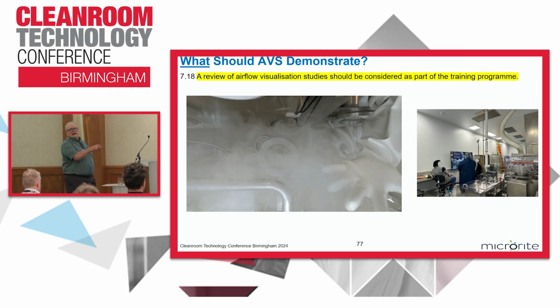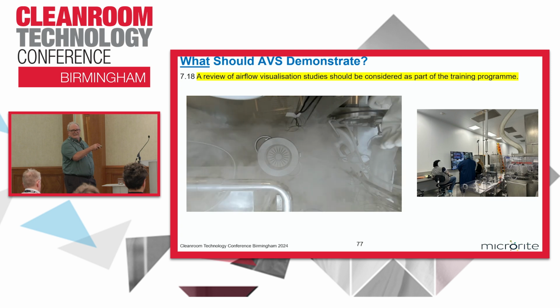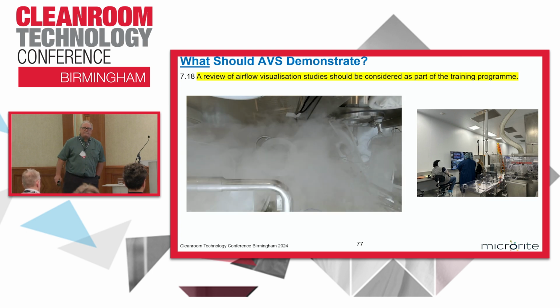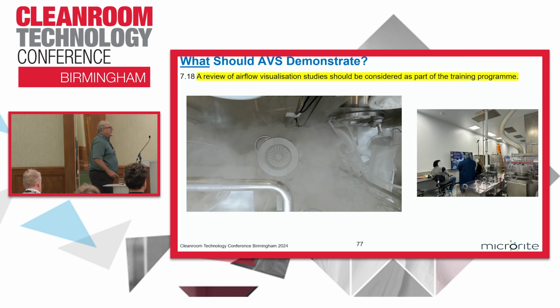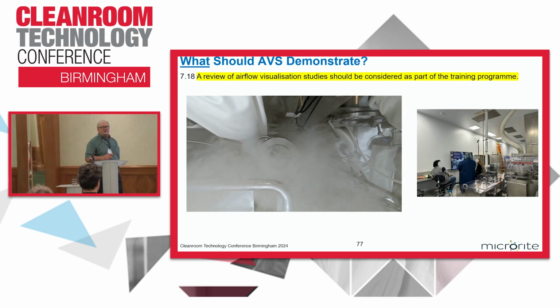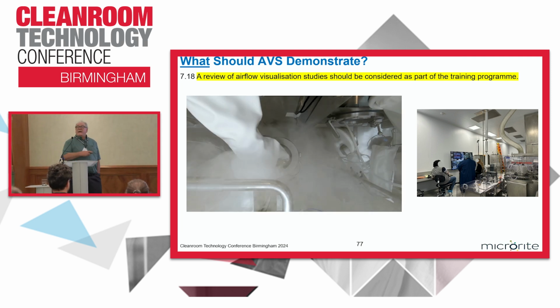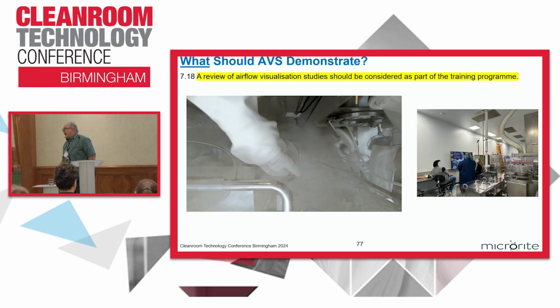That's an active air impactor, right? That's an active air sampler. The operator is using the sampler as a shelf for the tri-clamp for making the aseptic connection. Would that be a problem? I think it's a problem, right?